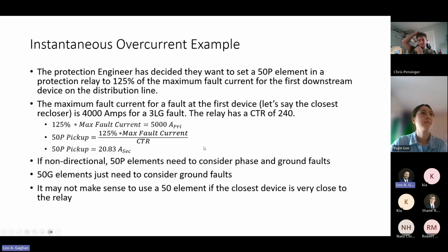So some extra considerations. If you've got a non-directional phase instantaneous overcurrent element, it needs to consider phase and ground faults, because a ground fault is going to have current on the phases. If it's a ground fault on phase A, it's going to see a lot of current. And then ground elements just need to consider ground fault current, since for three-phase or line-to-line faults you're not going to have any 3I0, so it just needs to consider the ground faults.